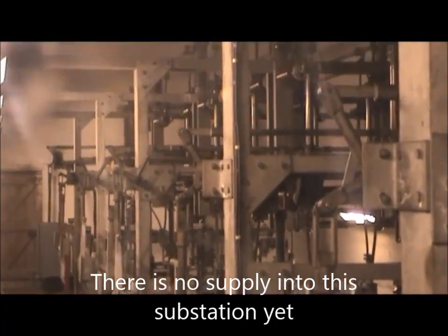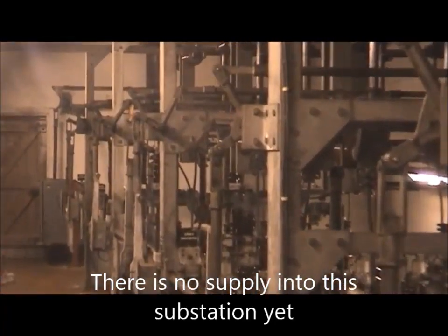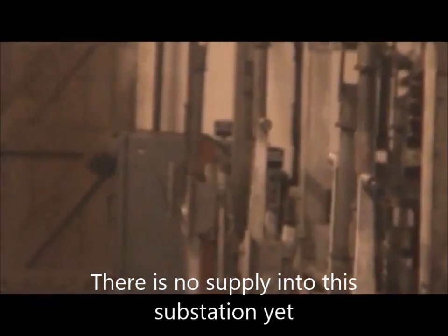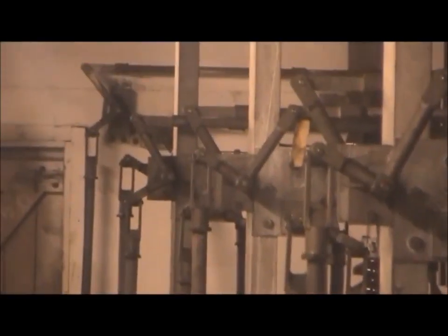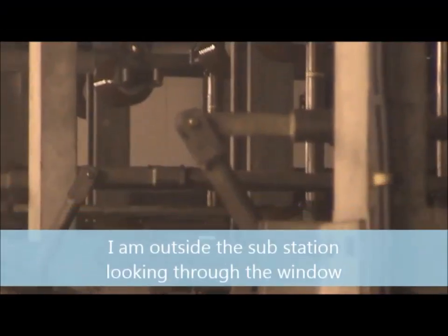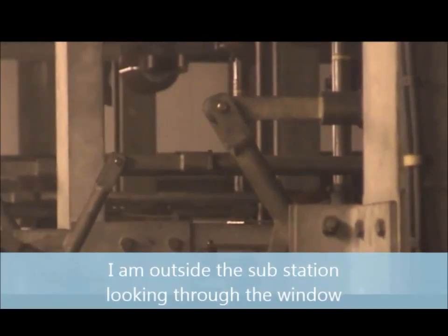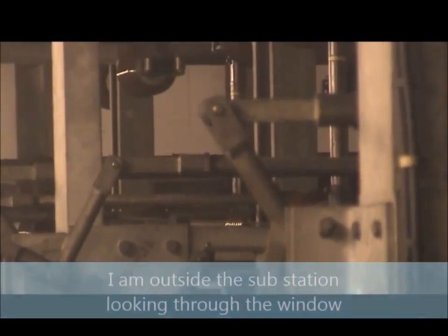This is the 33 kV offload isolator substation. You can see the motorised control units for feeder 1 at the far end now, which is going to operate the mechanism to close up the 33 kV. But at the moment the 33 breakers are open, so I can close this offload isolator from the local controllers here.